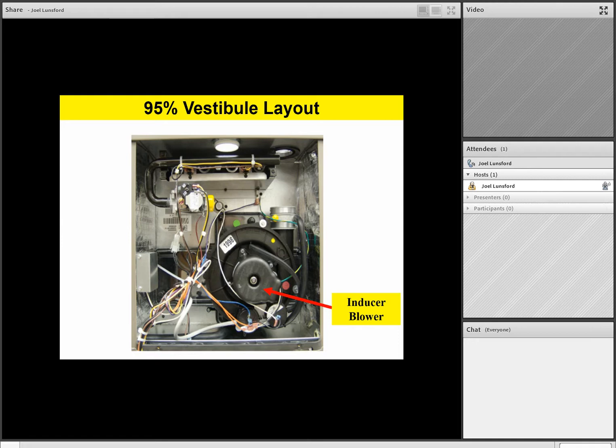There's the induced draft blower. Now we notice on our 95 plus furnaces that's going to be a high temperature composite material. We noticed on the previous slide where we had our 80% furnace, that was all metal. And so this is going to be a plastic or a high temperature composite material on the 95 plus furnaces. And look again, one more time, just a simple drain line goes out of the furnace instead of a bunch of complicated traps. So again, one of the real nice features about the Champion furnace is that on our 95 plus furnaces, we have this simple drain line and we don't have a bunch of complicated parts or traps that we have to deal with.